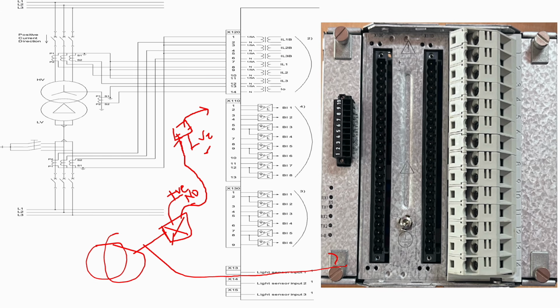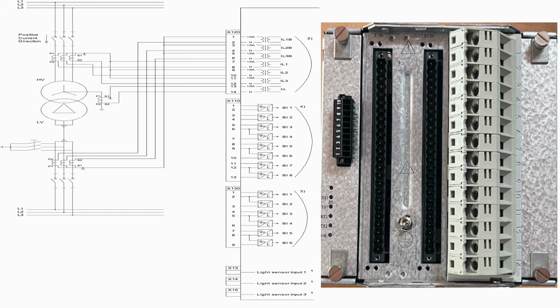So whenever my breaker remains closed, right now my breaker is off. Okay, suppose my breaker is on, this contact will convert NO to NC, and my positive here will extend through this terminal and connect to the binary inputs. So I can get indications like my breaker is on. This kind of indication, if we want it for any reason, for LBB, for indications, for interlocking, for any reasons, you can utilize these binary inputs for different reasons.